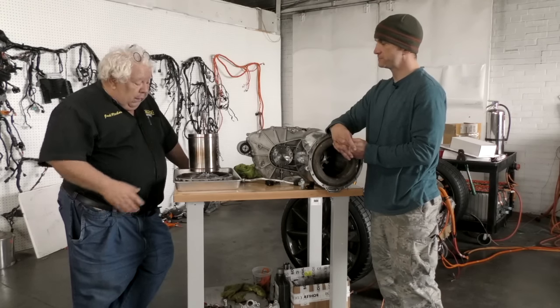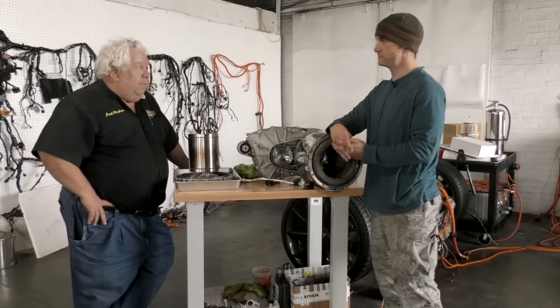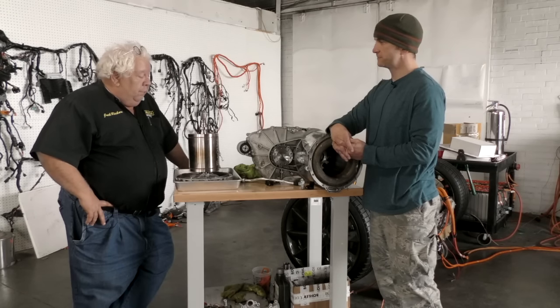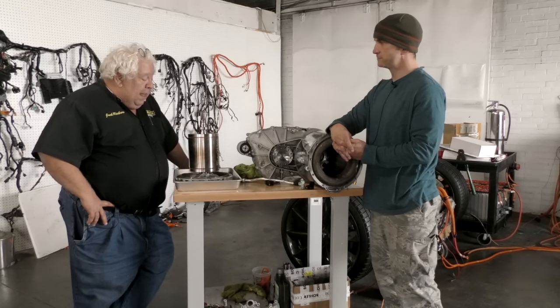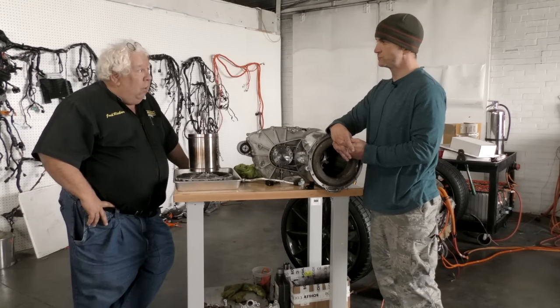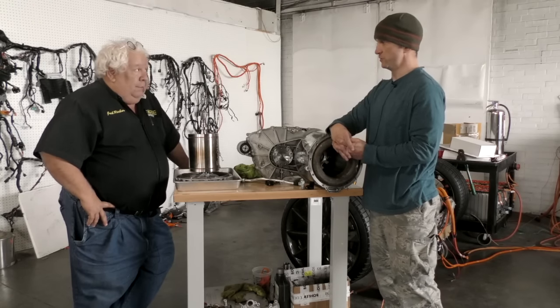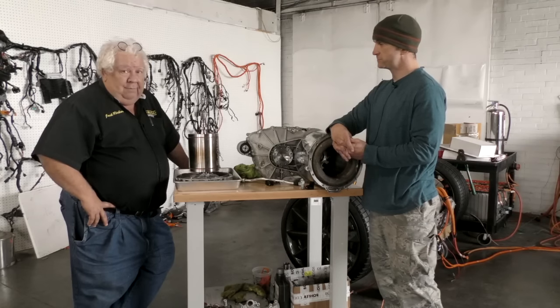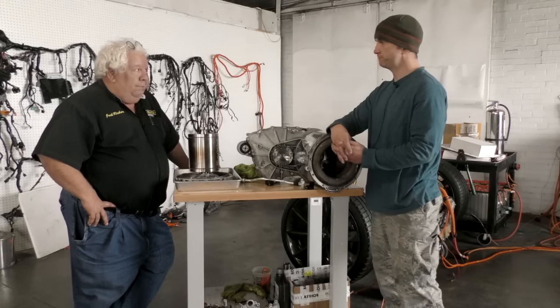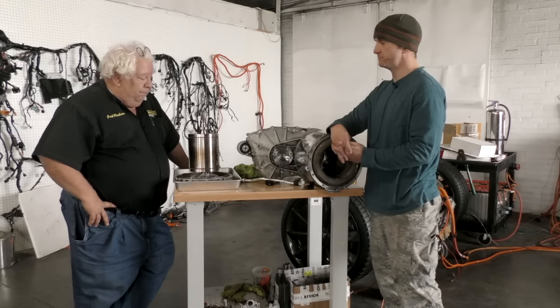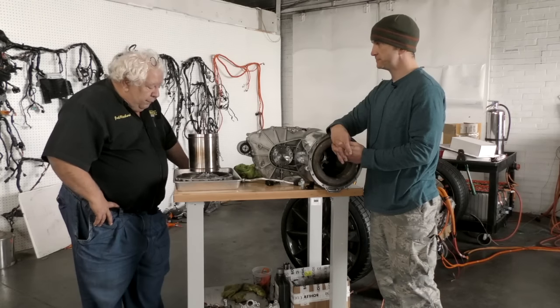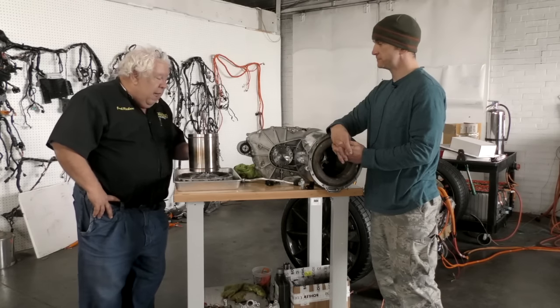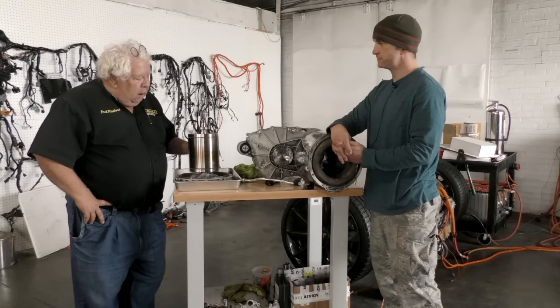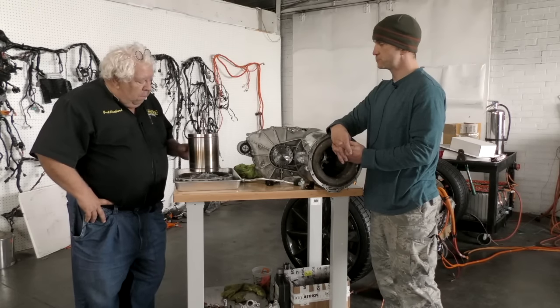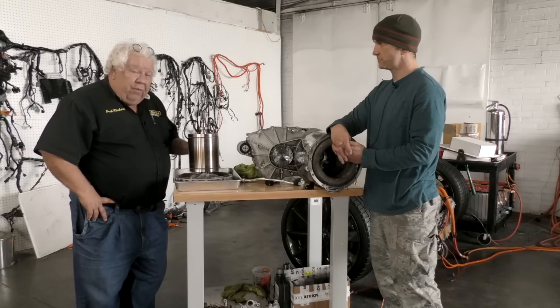And the only part left here is the bearing for the rotor, and it's not the kind of bearing that would bear a lot of wear. There's no load on it, it doesn't really have any thrust at all, just the weight of the rotor, which isn't that much. So I'm a little lost as to how that bearing went bad in obviously a young motor, but there's our observations.